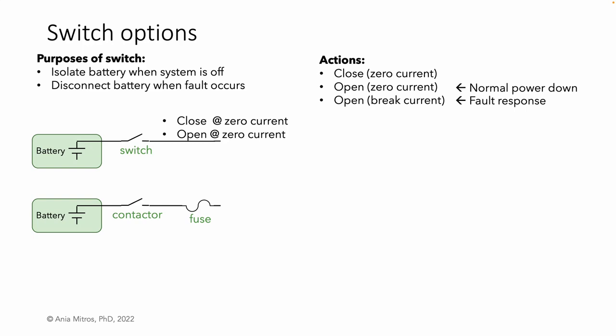We can select our contactor to break the maximum system current, but oftentimes a short-circuited battery may provide a current well beyond that. To protect against high currents, we add a series fuse. We split the protection function across two components. Note that a contactor can open repeatably, while a fuse creates a permanent open.